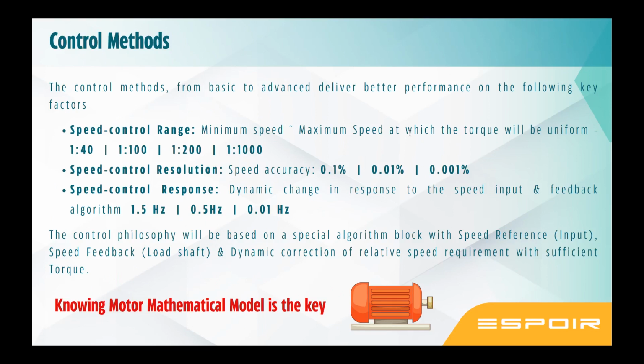Now, achieving range is one aspect. Another aspect is the resolution. Means we are trying to achieve, but how accurate they are. In a V/F method, the accuracy is very poor compared to what you can achieve in the closed loop method. It could be as poor as 0.5%, 1%, 2%, depends on the software function, depends on the algorithm they have created, depends on the programming you do, and also the other aspects of selection and engineering.